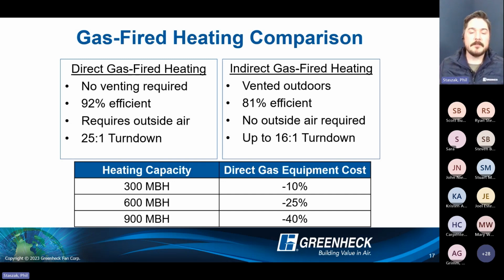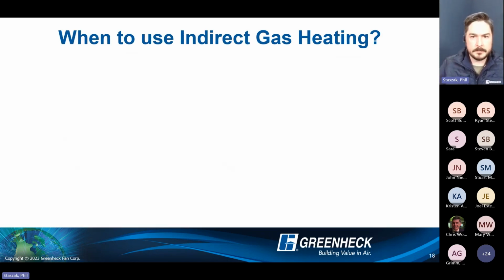We go all the way up to a 10-foot burner here at Greenheck, and that's where we can move 65,000 CFM of outdoor air and offer up to 7.2 million BTUs of heat. And regardless of where the electrification conversation goes, I don't know where we're generating 7.2 million BTUs of available capacity by any other means right now, aside from burning natural gas or liquid propane. So that's another interesting part as far as the more heavy industrial applications. I don't know how much of that you guys are doing work on, but just something to consider.